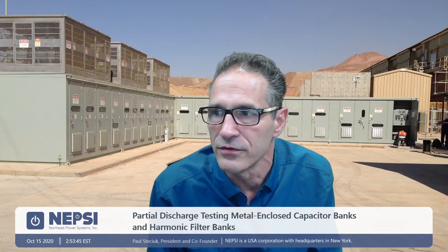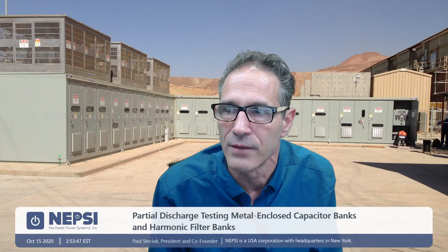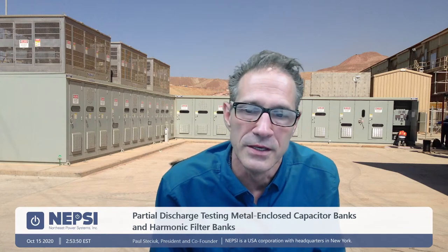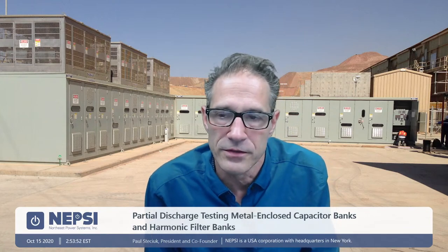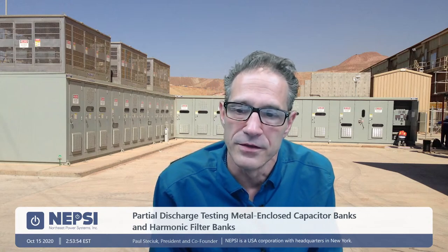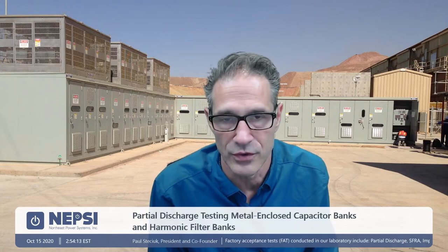There is a question: with the insulation strength of air being 21 kV per centimeter, is there any value in testing for corona on equipment that will operate below this voltage? I think the real question here is, do we get to the voltage stress level where we can have partial discharge in the equipment? And the answer to that question is yes. We have already identified multiple problems in our equipment at the 38 kV and below level, for which the voltage stress can exceed that of air and can cause problems in the equipment.